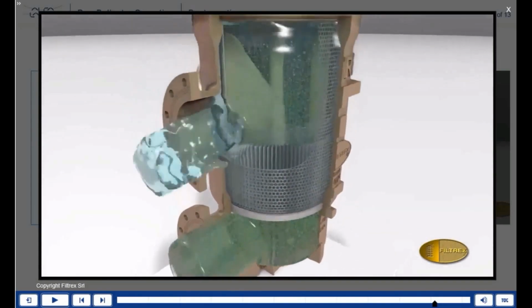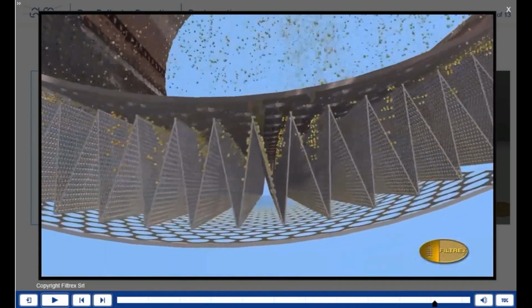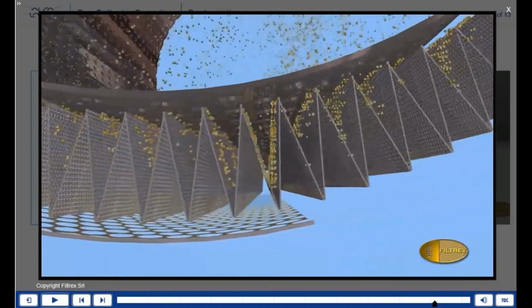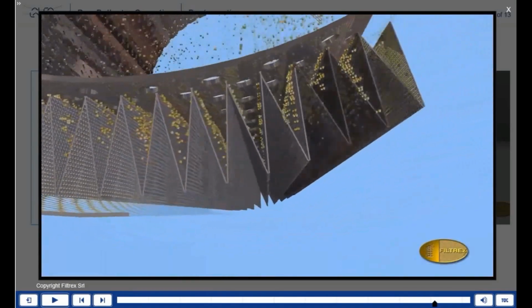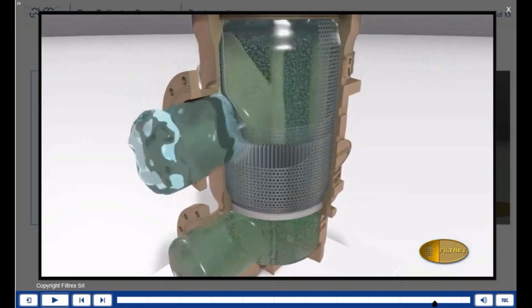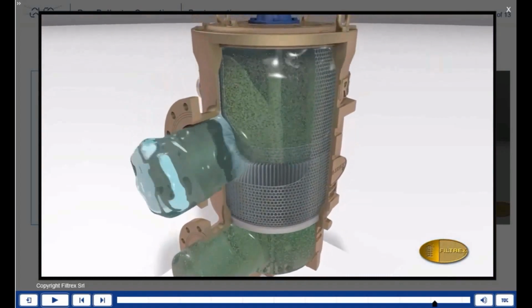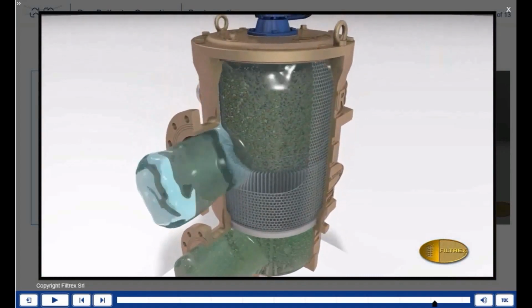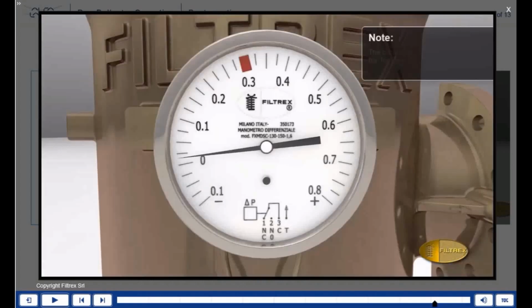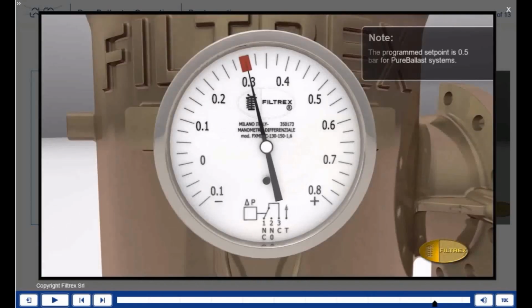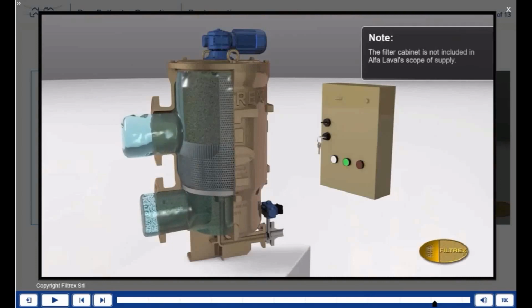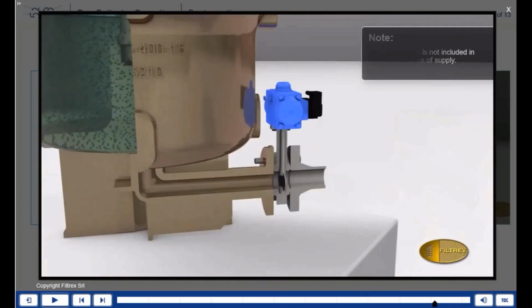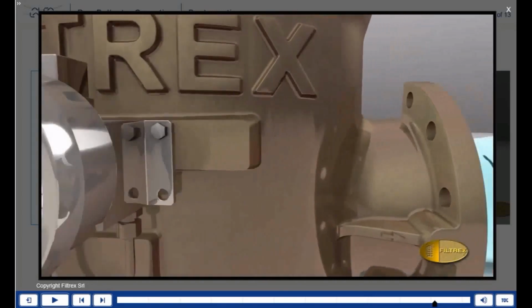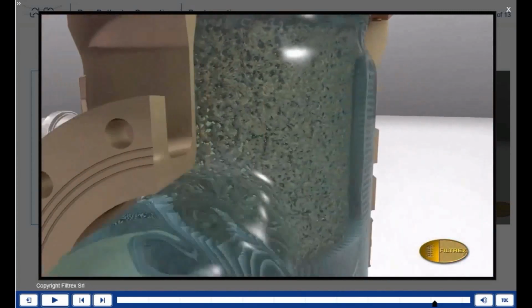During this phase, the filter operates as a static filter and the cleaning of the filtering element is inactive. As more and more impurities build up in the filtering element, the differential pressure gradually increases, as shown by the indicator, until the programmed set point is reached. Through the control panel, the electric motor is activated, then the backwash valve is opened, starting the rotation of the cleaning nozzle and the cleaning phase.